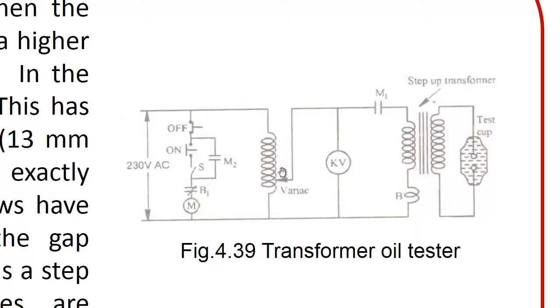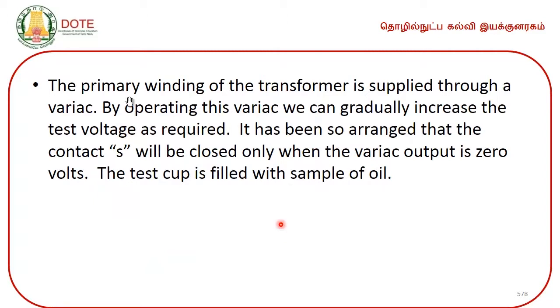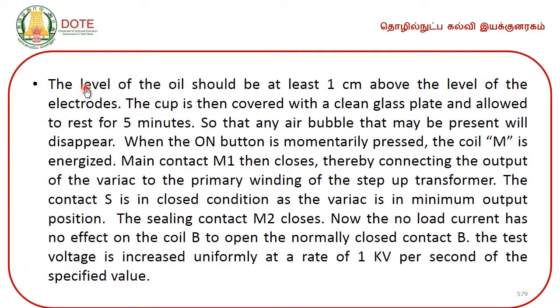By varying the auto transformer sliding contact, you can vary the magnitude of the input voltage applied to the primary. Now, the primary winding of the transformer is supplied through a variac. By operating this variac, we can gradually increase the test voltage as required. It has been so arranged that the contact S will be closed only when the variac output is 0 volts. The test cup is filled with a sample of oil. The level of the oil should be at least 1 centimeter above the level of the electrodes. The cup is then covered with a clean glass plate and allowed to rest for 5 minutes, so that any air bubble that may be present inside will disappear.